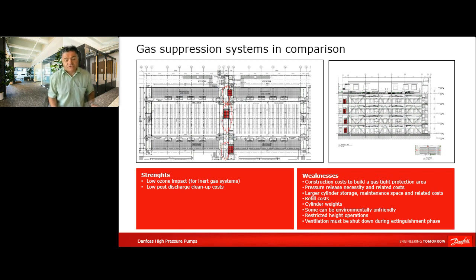But the gas suppression system also has some disadvantages when you compare it to a high-pressure water mist system. First of all, you need to make all those rooms where you want to distribute the gas gas tight. You have to insulate them. You have to make them ready in such a way that the concentration of gas remains in that room in order to extinguish the fire. Otherwise, the gas would flow away, and then you will never reach the minimum necessary concentration of the gas. In a high-pressure water mist design, you don't need that.